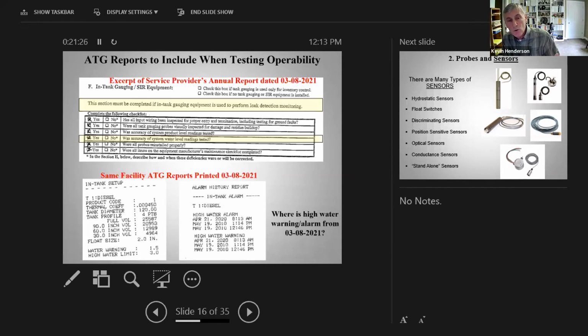And so the way we do that, of course, is print the alarm history report to show that, yes, the water alarm did go off on the same date that I did the testing. In this example, it was March 8, 2021. So if you look at the two Veeder-Root reports that go along with this annual testing report, you see the in-tank setup. Okay, that's great. But then you see the alarm history report for the in-tank alarm, and you do not see any high water alarm or warning for March the 8th, 2021. The last one was over a year ago, in April of 2020. So even though this guy was there on March 8th and said he tested the water floats, he did not show me that. He didn't document that. It looks like he just checked the box.